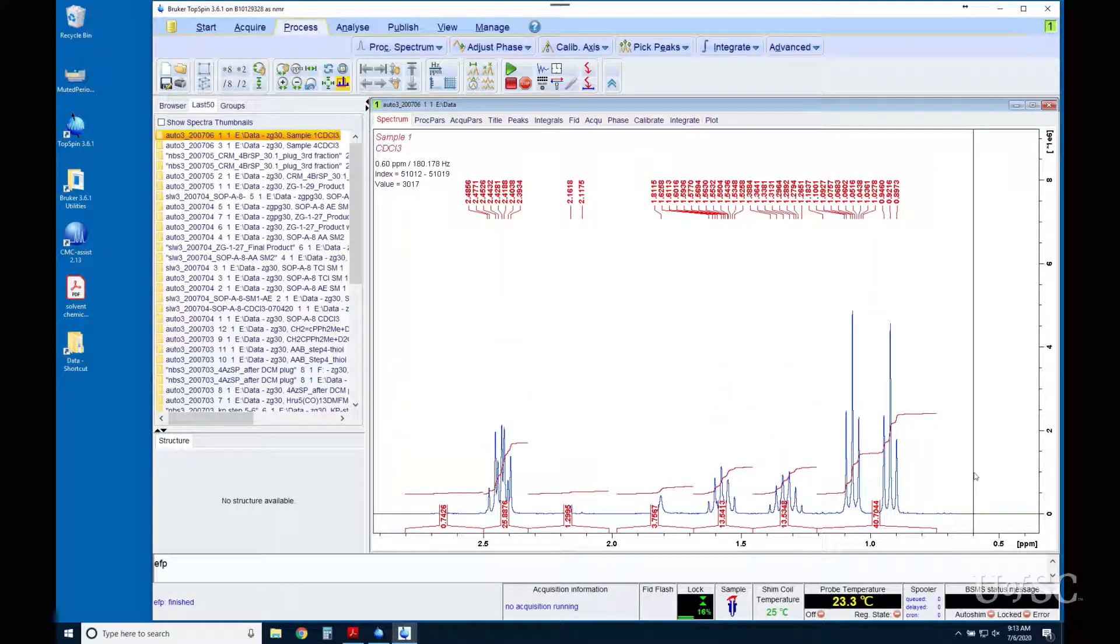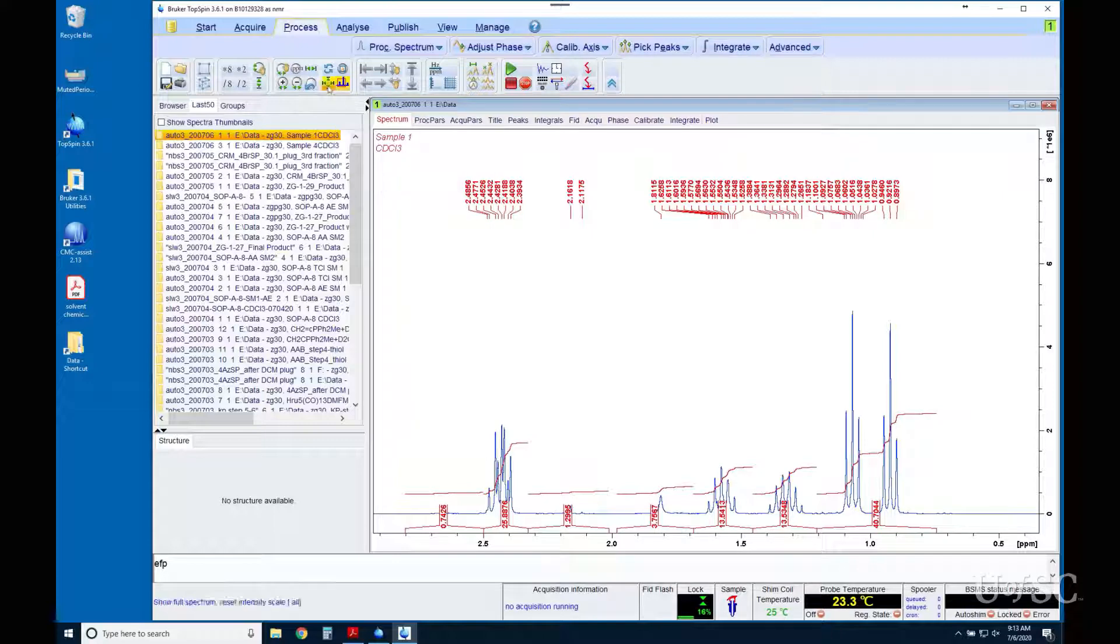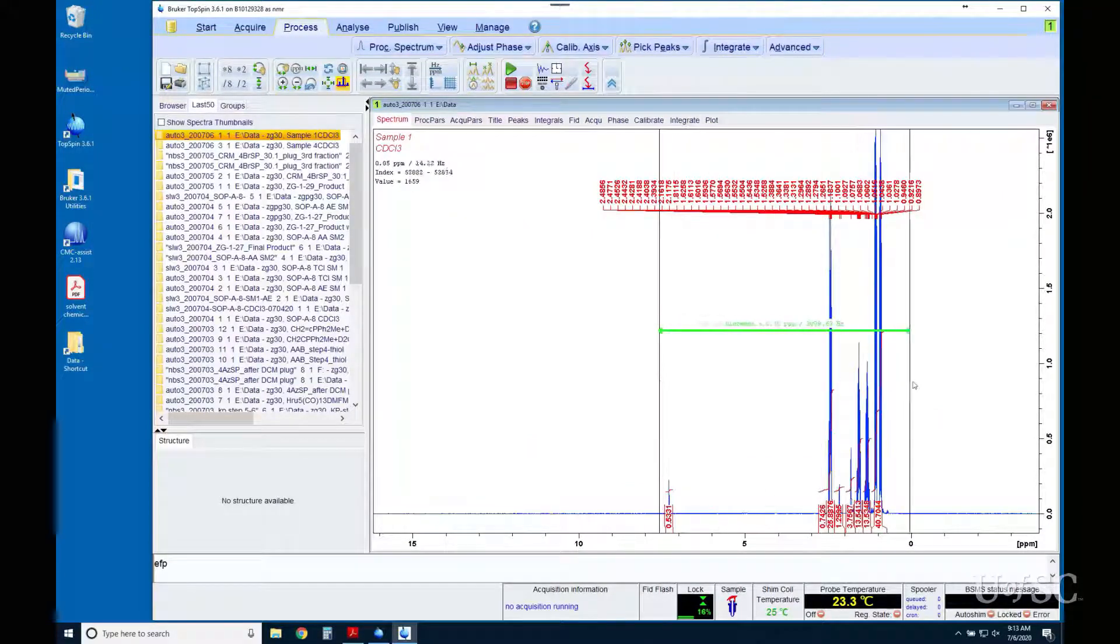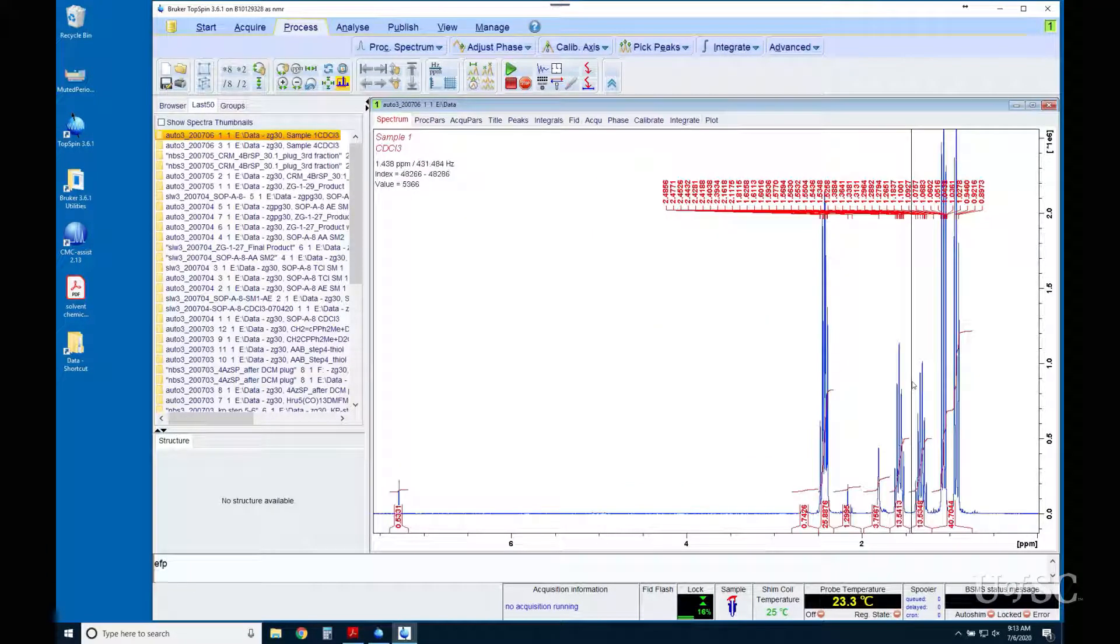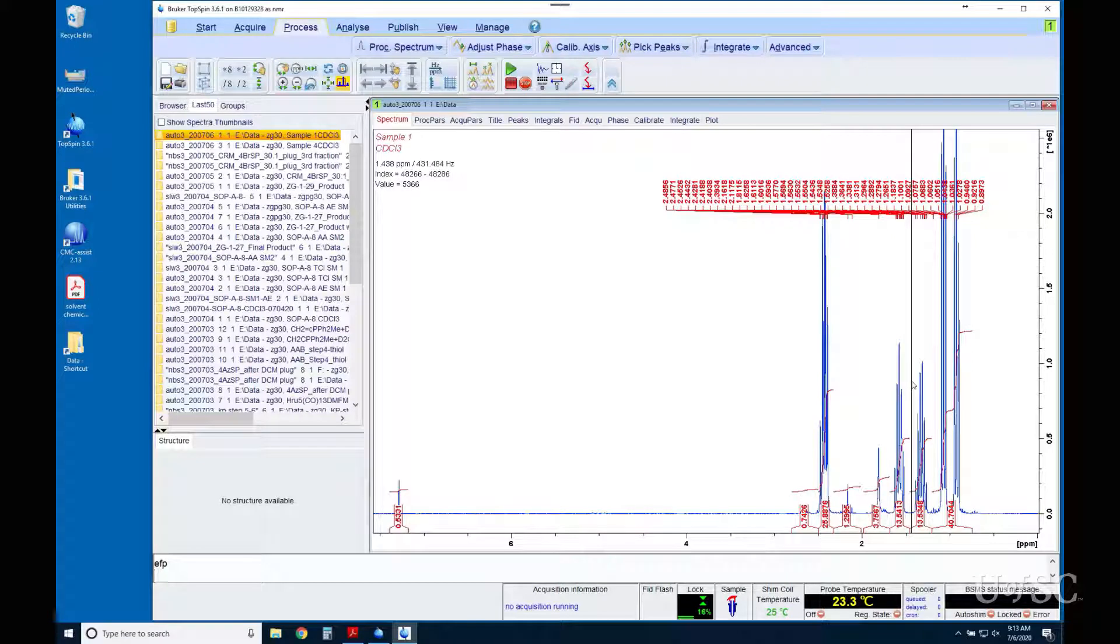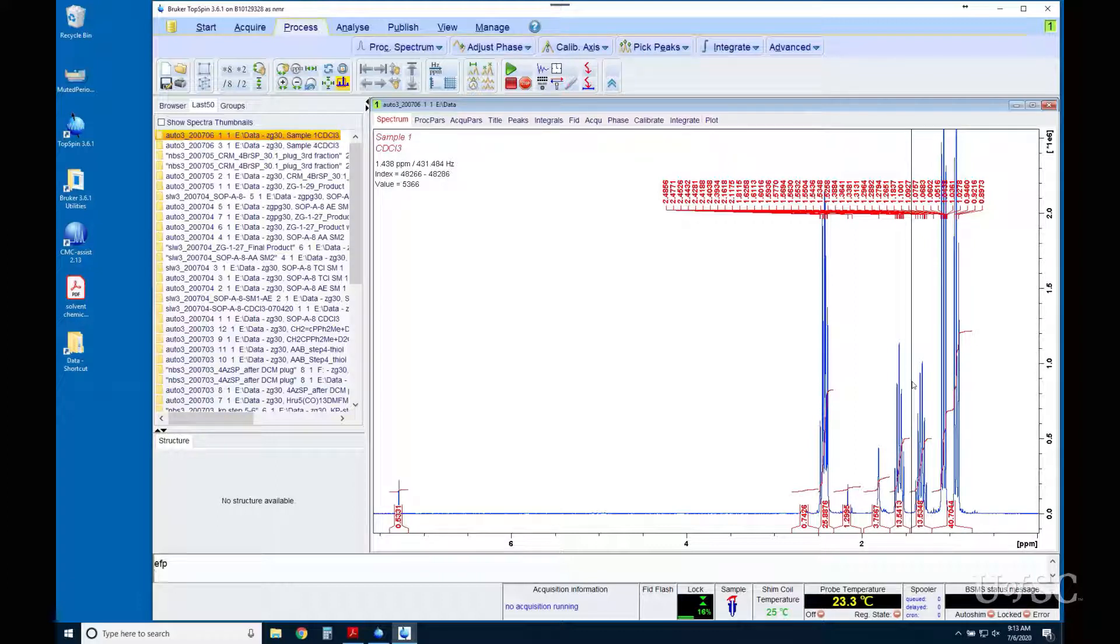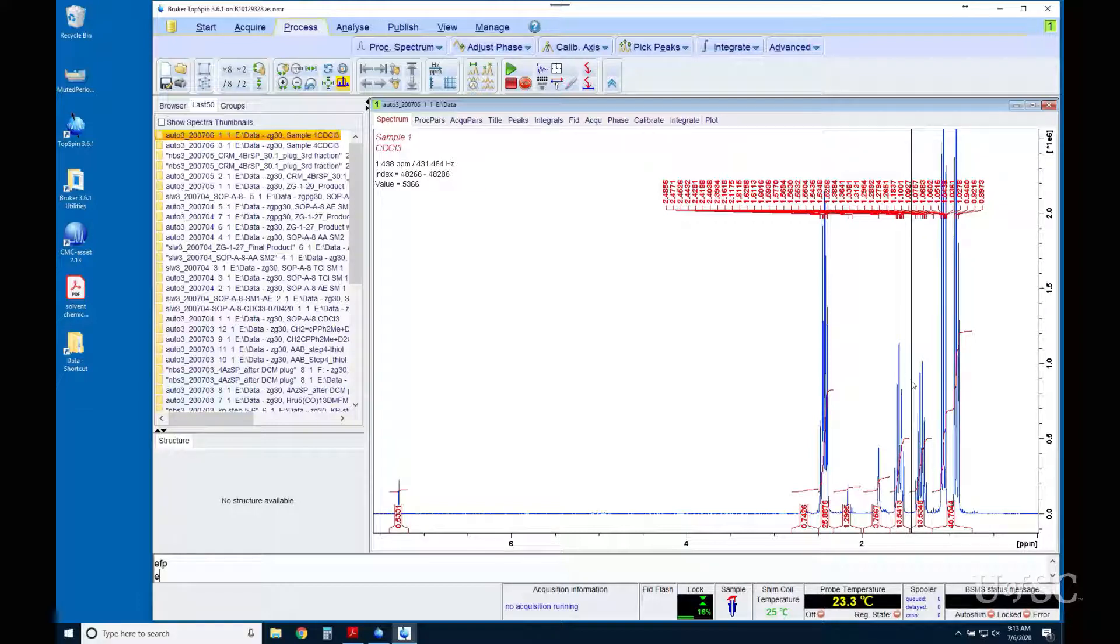The P in EFP is a phase correction. This just applies the last phase correction, so if it was okay before, it should still give you a correctly phased spectrum. However, if the phasing was not correct the result will still be misphased. To show the spectrum without the phase correction, in this case what the automation performed, you could use the EF command.